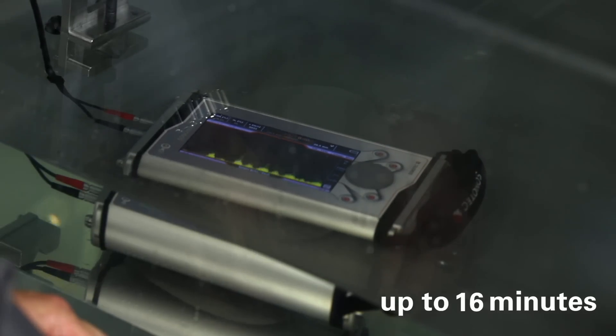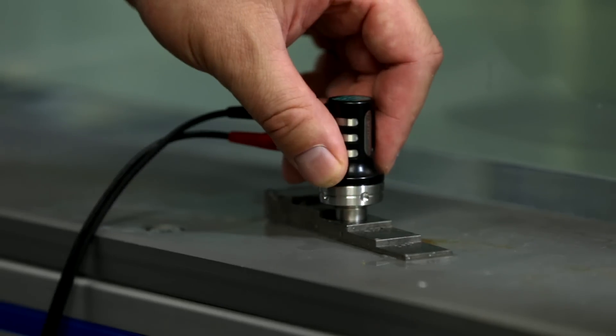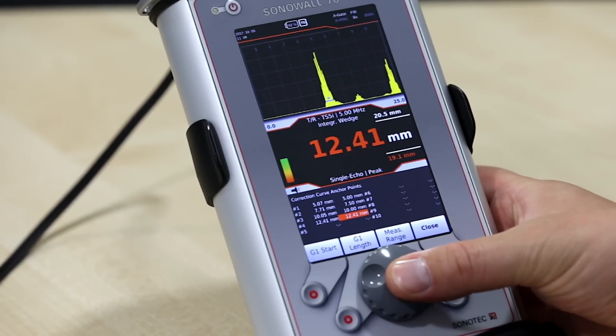The SONOWALL 70 has a powerful pulser equipped with a fully adjustable square wave pulser which can work up to 400 volts. The battery lasts for more than eight hours. All these features make the SONOWALL 70 the best companion in everyday ultrasonic testing.